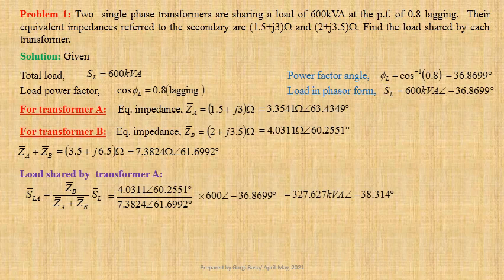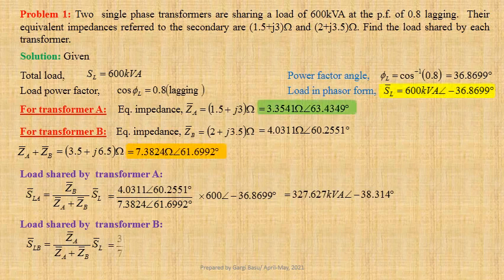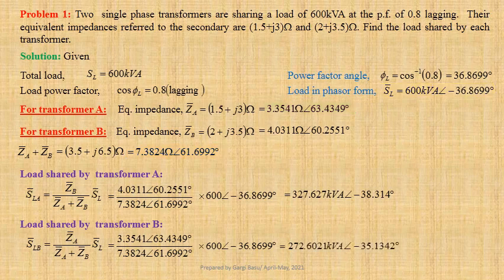38.314 degree. Load shared by transformer B, SLB equals ZA divided by ZA plus ZB into SL. Using values, we get 3.3541 at an angle 63.4349 degree divided by 7.3824 at an angle 61.6992 degree into 600 at an angle minus 36.8699 degree. That gives us 272.6021 kilovolt ampere at an angle minus 35.1342 degree.